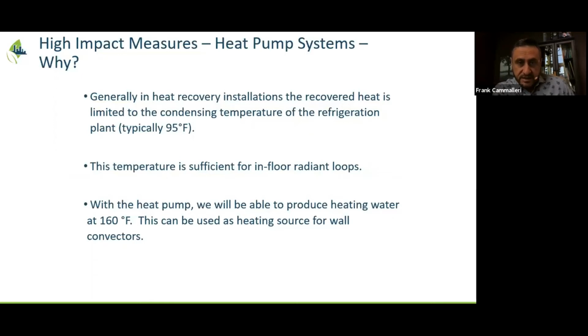One of the things that motivated the use of the heat pump or heat recovery chiller is the fact that the temperatures available through the refrigeration system, on the condenser side before the heat is rejected to outside, are typically lower, around 95 degrees. It could be as high as 110 degrees as well, which is okay, but it's usually not sufficient for too many sites. It's fine if you have, say, in-floor radiant heating. So it's great if you have a new facility and would like to design for the lower temperatures; in-floor radiant heating is a good option. But again, we're dealing a lot with existing structures, and a lot of them don't have that feature.